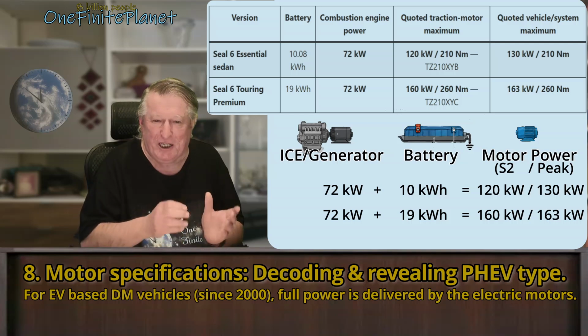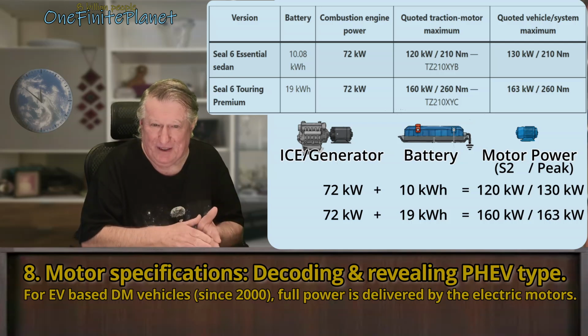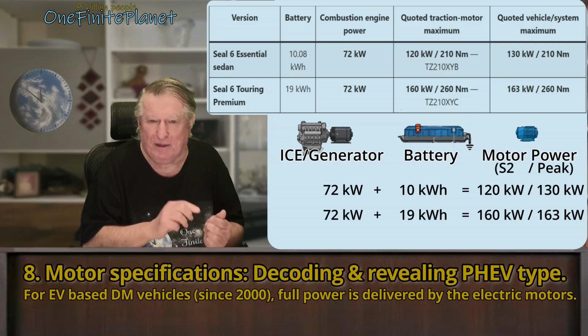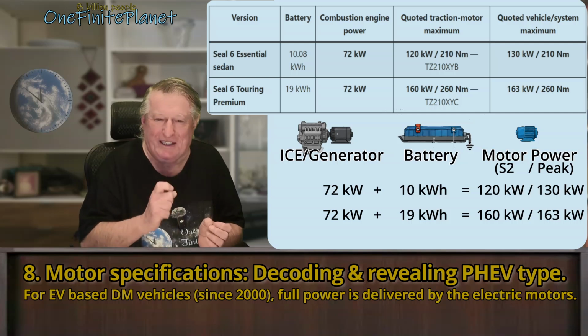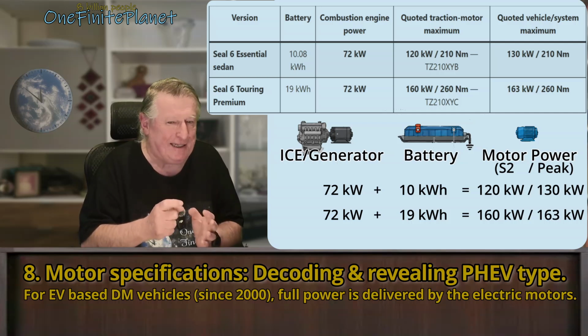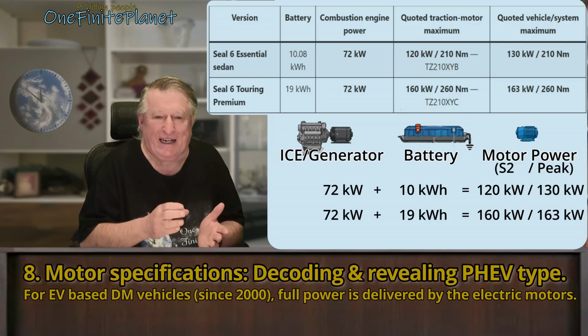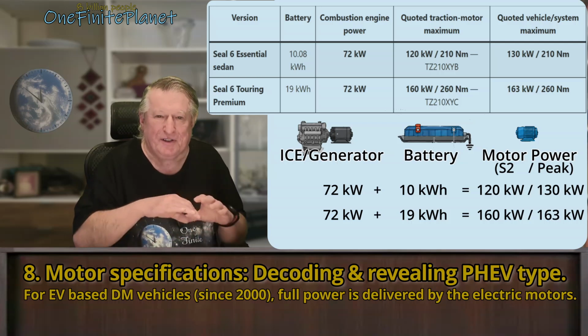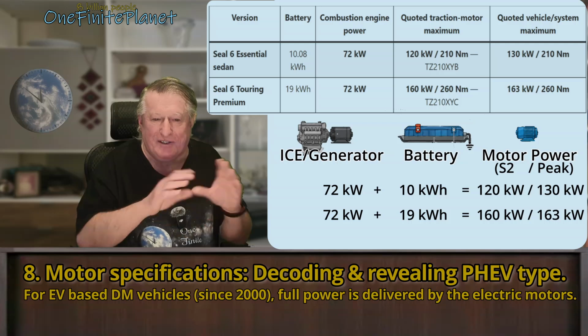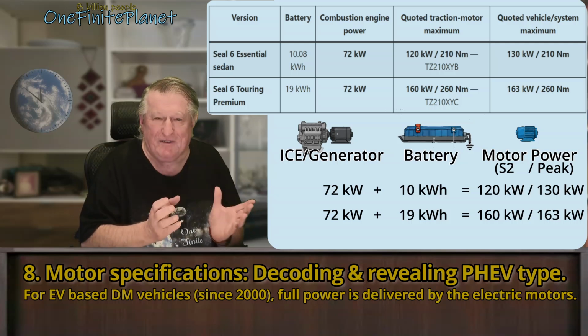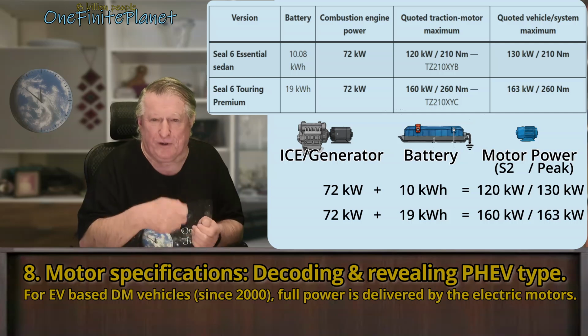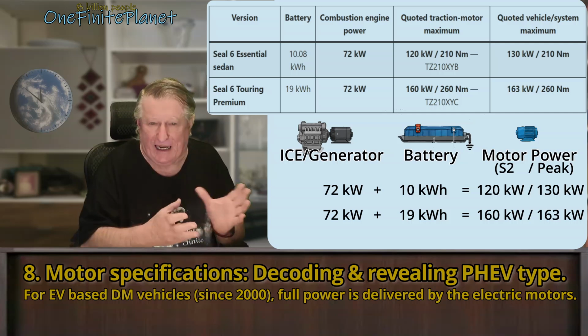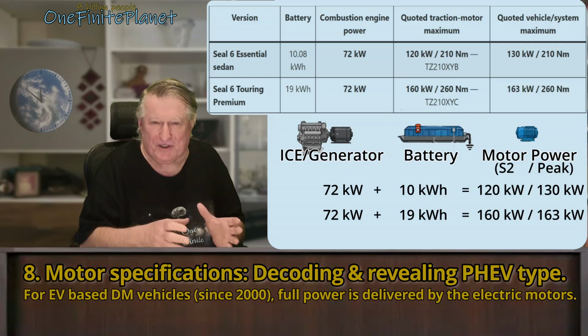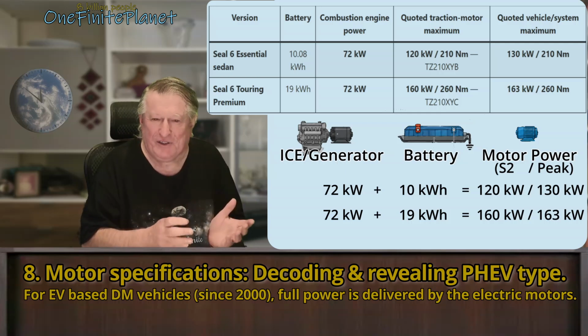Another secret here can be read from the details on the motor. We've got a TZ210XYB and a TZ210XYC. Only one letter difference between these seemingly quite different motors. And in fact, the 210 is the stator core or outside casing diameter. Physically, these two motors are going to be the same size. They could technically use different electrical windings or different quality magnets, but overall, when you look at the cost savings that can generate, it quite often isn't worth it.